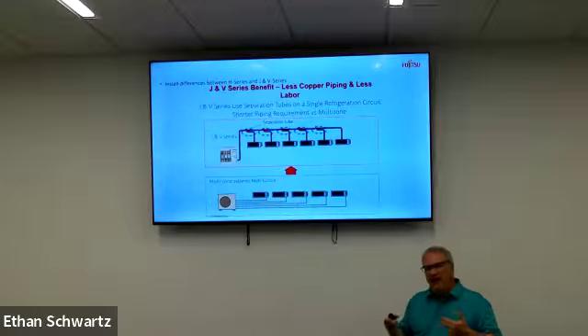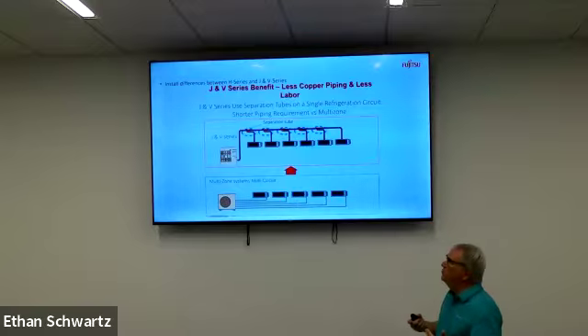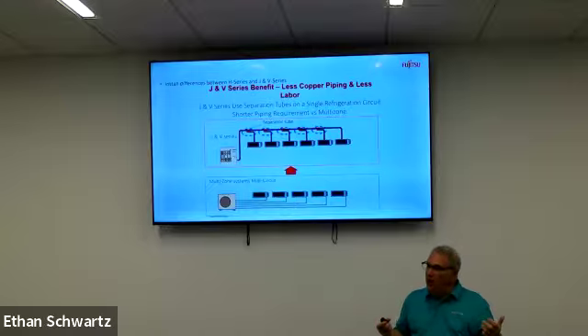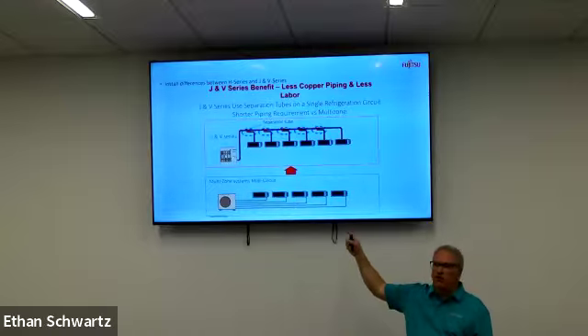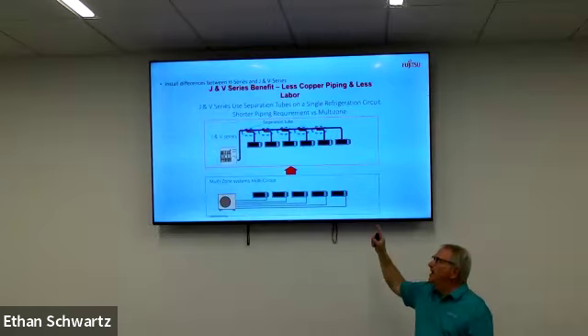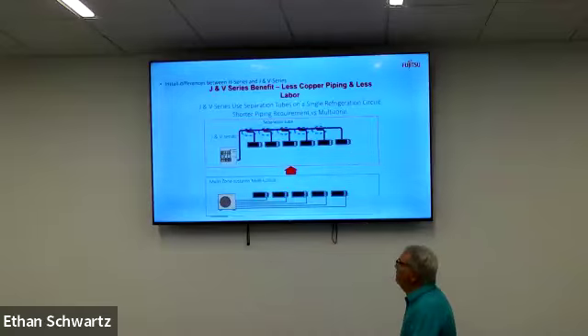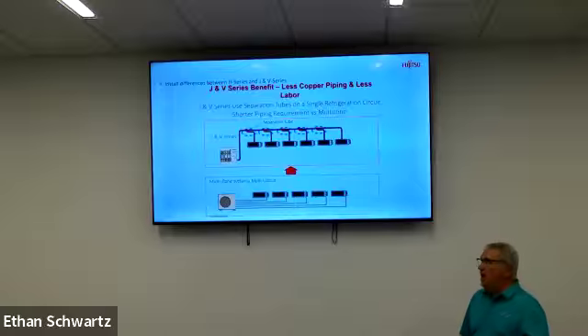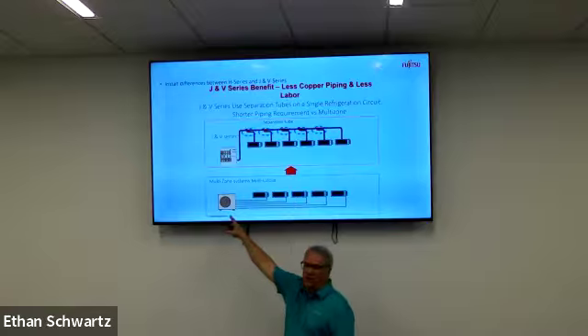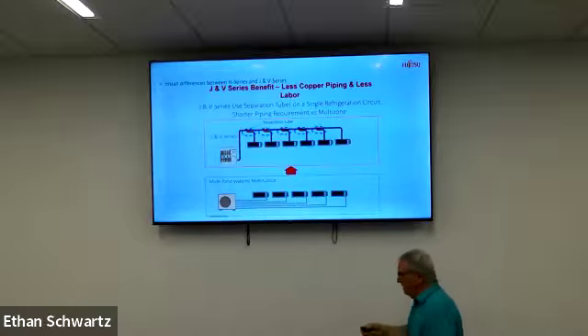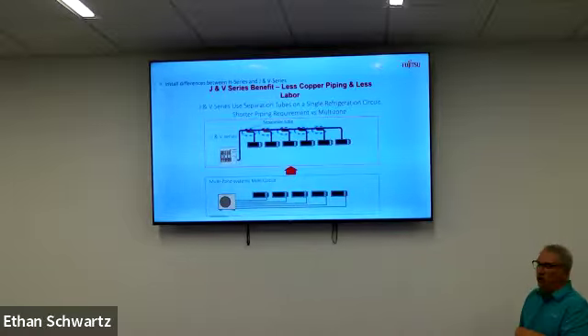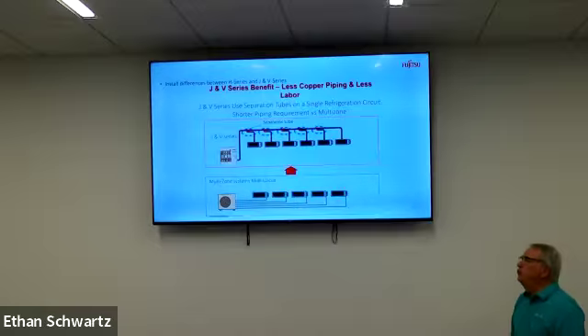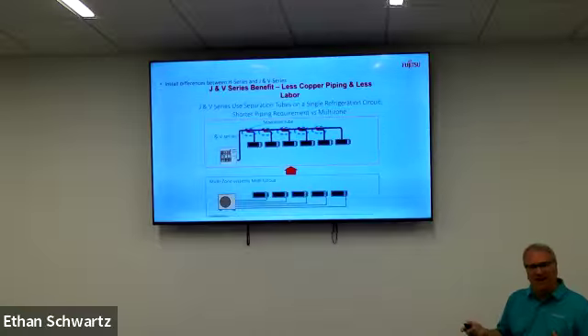So be sure to ask the customer, okay, what are you looking for with the single zone system? Do you need a longer line set length? That's going to drive the choice to the J series, that long line set length. Over what might happen with the multi or single zone system, because the EEV in a mini split is located in the outdoor unit, and the EEV in the VRF is located in the indoor unit. So we have a true liquid line going all the way out to the indoor. Does that make sense to everybody? Is that anything new? Does that help to kind of drive it home?